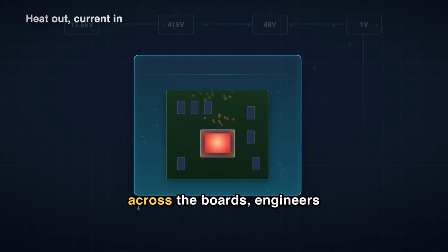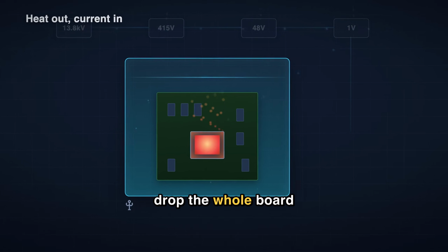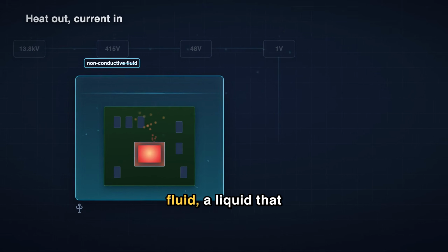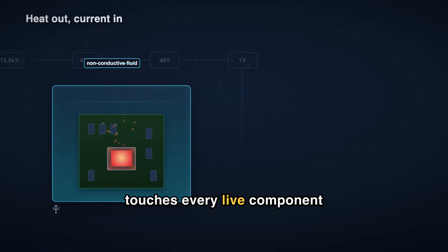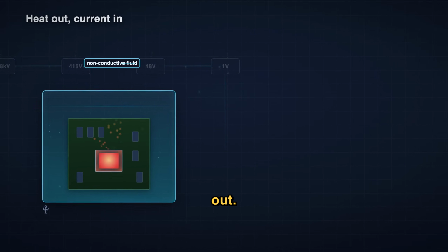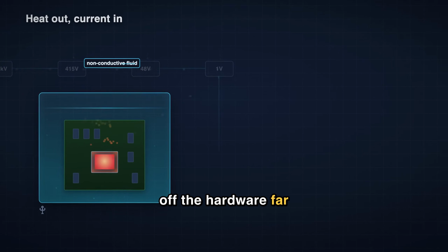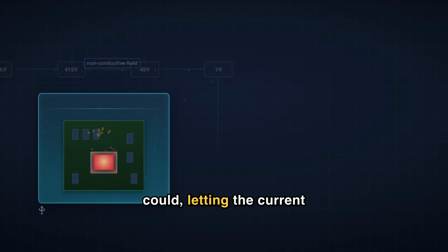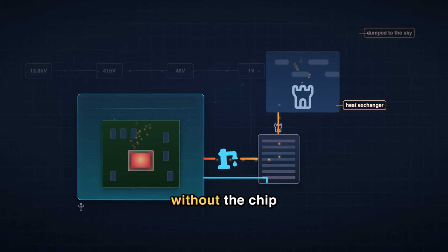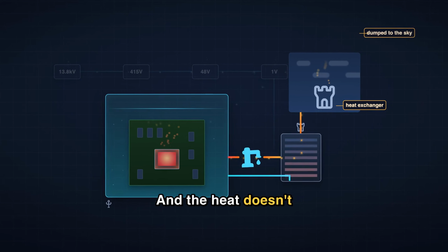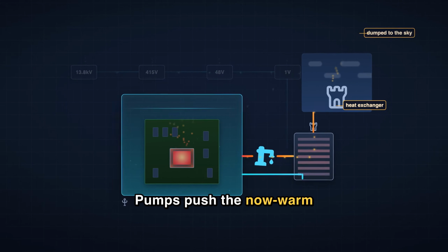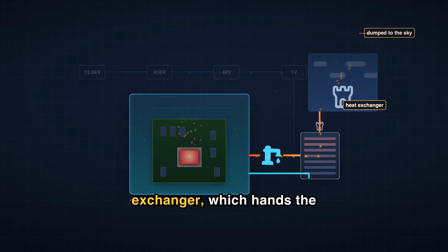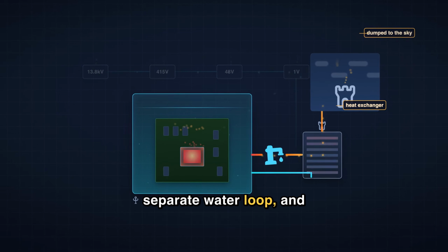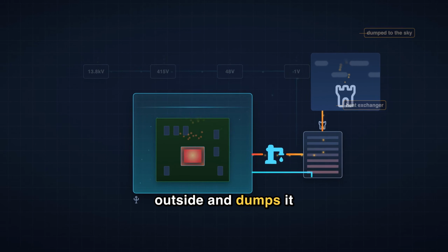Instead of blowing air across the boards, engineers drop the whole board into a bath of special non-conductive fluid, a liquid that touches every live component without shorting anything out. That fluid pulls heat off the hardware far faster than air ever could, letting the current density stay brutally high without the chip overheating. And the heat doesn't stop there. Pumps push the now warm fluid through a heat exchanger, which hands the heat off to a separate water loop, and that loop carries it outside and dumps it to the sky.